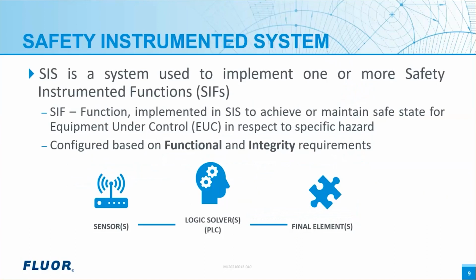SIS is a combination of hardware and software. It is configured to take automatic actions when the process deviates from the normal operating range. The safeguarding functions implemented within the SIS are termed safety instrumented functions, or SIF, and it has two major attributes: the functional requirement and the integrity requirement.